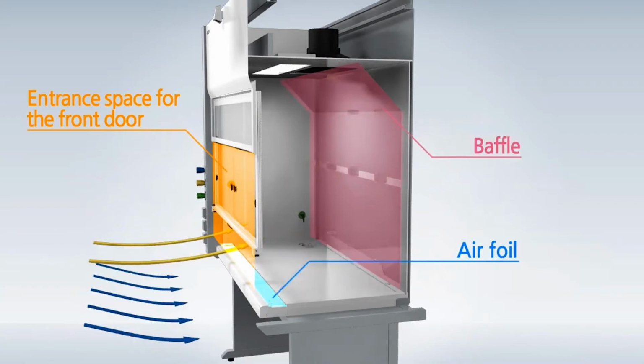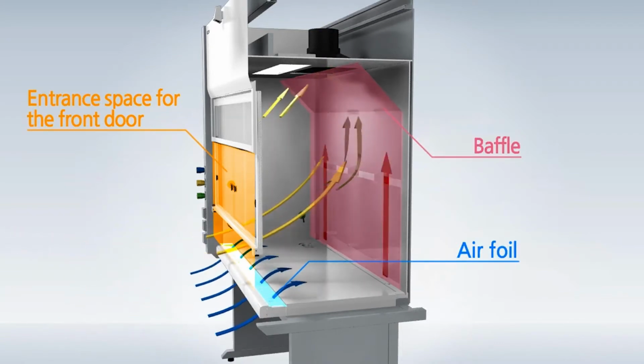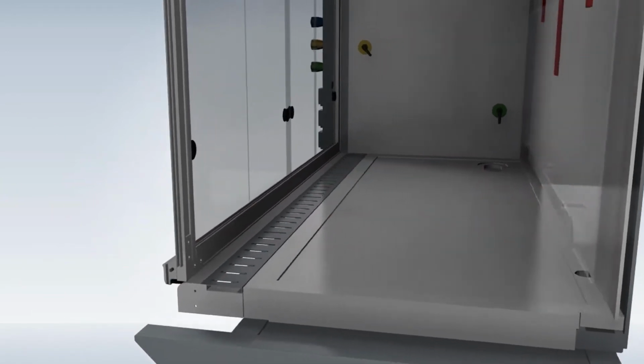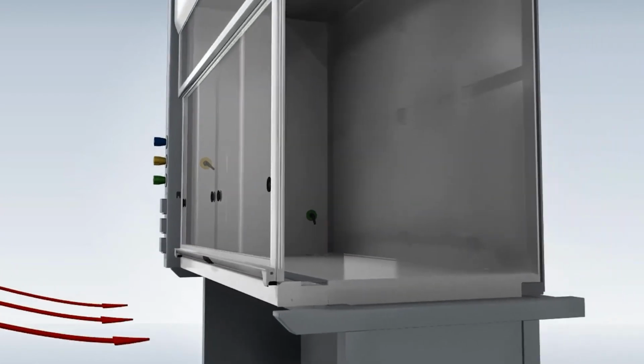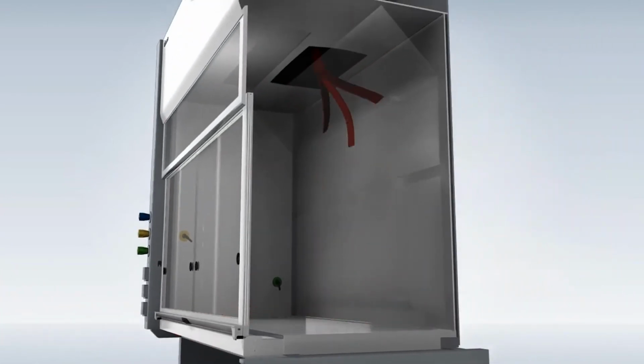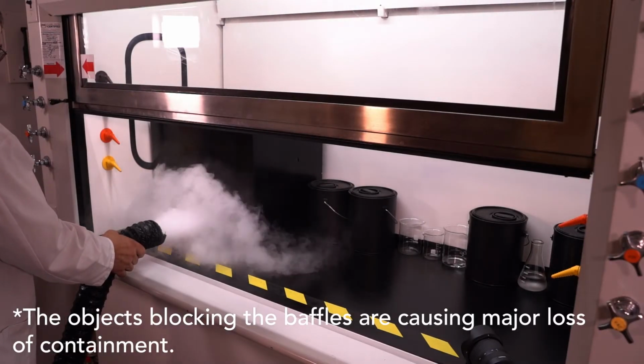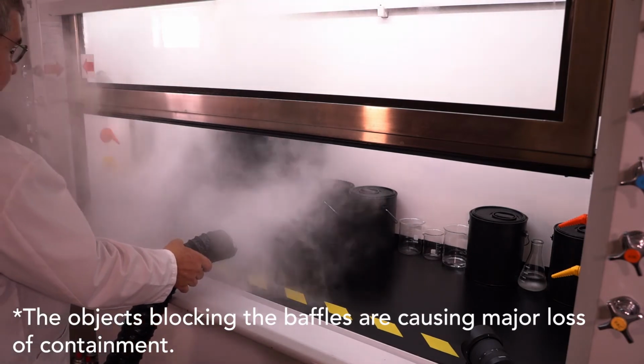While this all looks simple on paper, it's anything but simple in reality. Maintaining proper balance is critical to the hood's safe performance. Airflow is typically not something the user can control, but it is necessary to have a general understanding to verify that the hood is working properly. But there are some components of airflow that the user can control. Let's say that everything is balanced and working properly. There's air entering the fume chamber through the sash and over and under the lower airfoil. Given the pressure difference, the air is trying to flow across the work surface to the lower slot in the baffle. But if there's objects directly on the work surface or in front of the baffles, you disrupt that airflow.